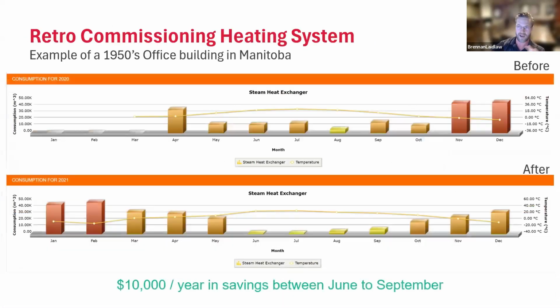But now I want to go into actual buildings. So this was an example of using data analytics as a retro commissioning tool. This was a large office building in Manitoba, where we applied it in April of 2020, and data started flowing in. Immediately what we saw was we're looking at a steam heat exchanger, by the way, which converts steam to hot water. And we noticed right away that, okay, in the summertime, it's using energy. It's using a fair bit of energy. It's using a lot less energy than the wintertime, but why is it using so much energy?